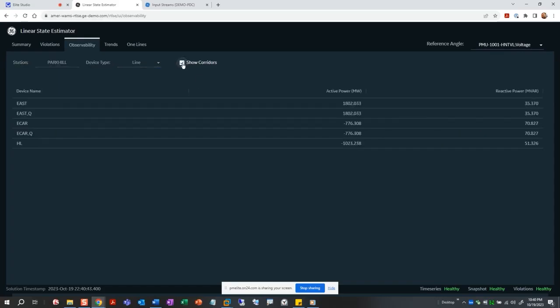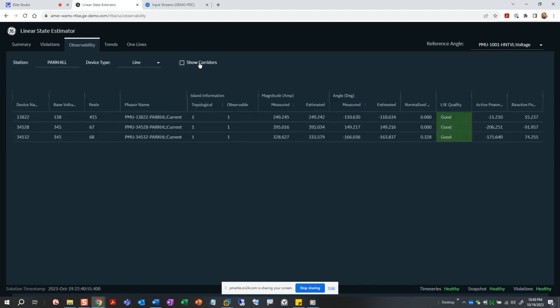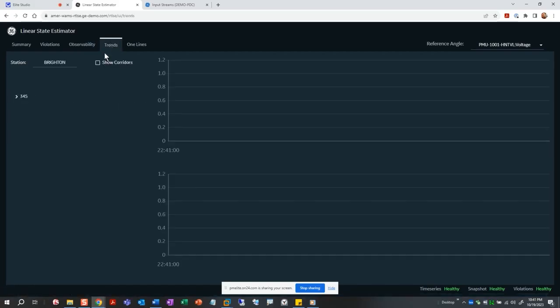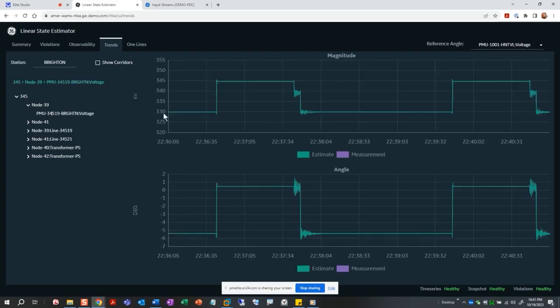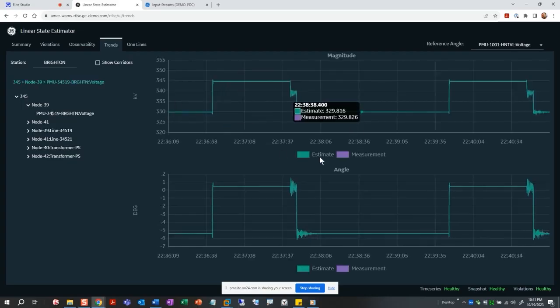The show corridors, that's essentially just a summary display that's showing all the different tie lines. So again, the tie lines that connect your electrical grid to your neighbor's grid. And turn those back off. And then the trends. So we can trend any value that we want in the system. So if we wanted to look at the Brighton voltage, we want to make sure that our estimated values are in line with our measurements.